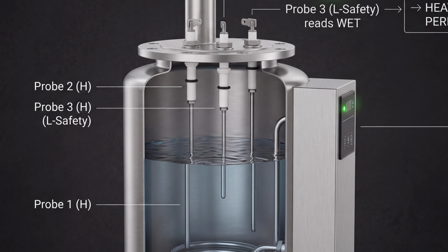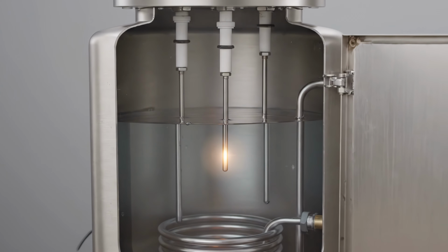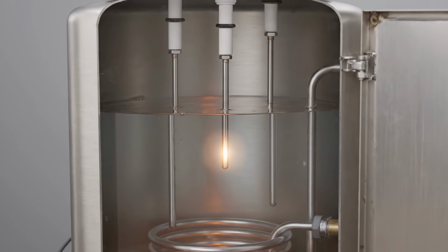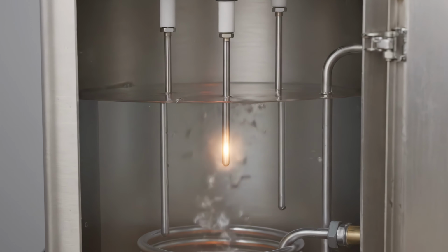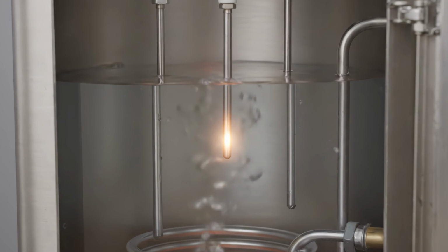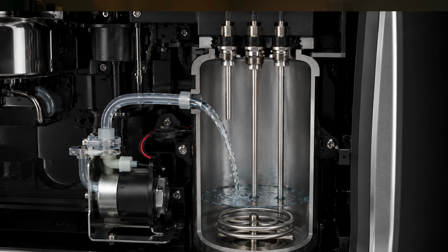Now, there are several water level probes inside the steam boiler, and they don't all have the same job. One is involved in controlling the fill level. If that signal is wrong, the machine may believe the boiler has enough water before it actually does. But that's not the probe I'm most concerned about. These three probes do not all have the same job. The short probe is the high-level fill probe. When the water falls below it, the machine calls for a refill. When water reaches it again, the refill pump stops.